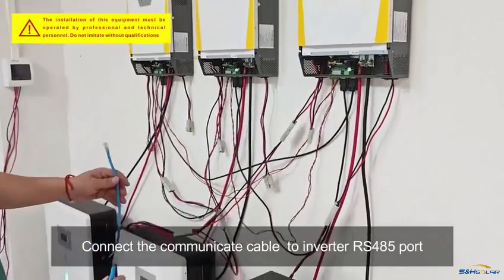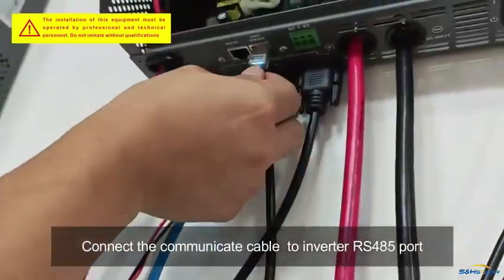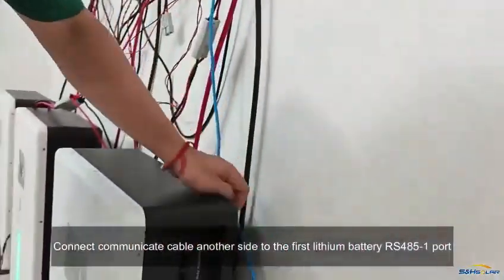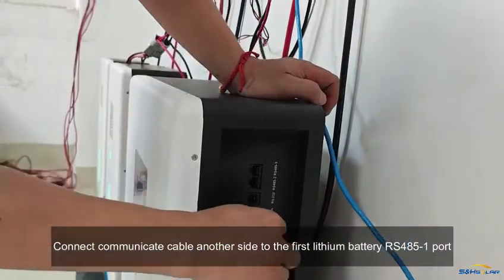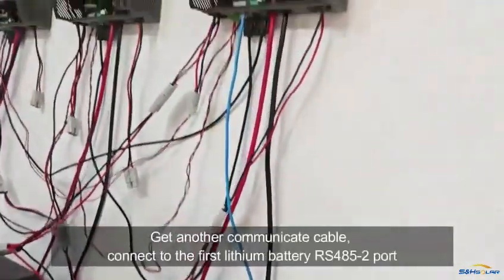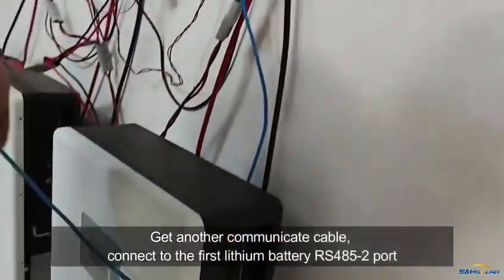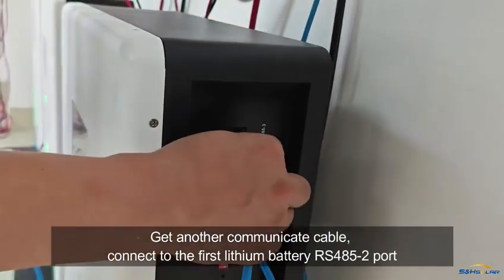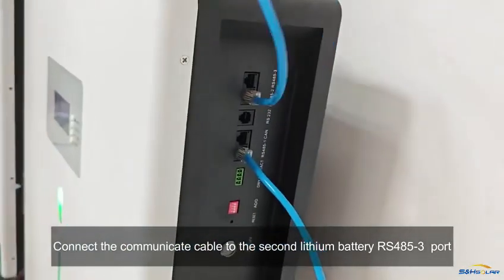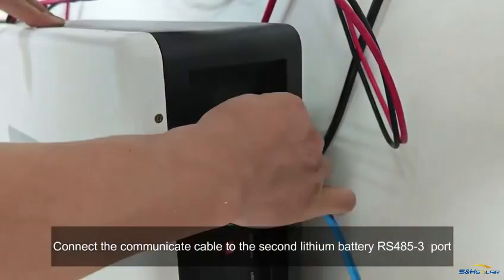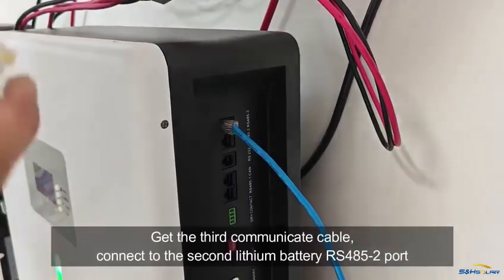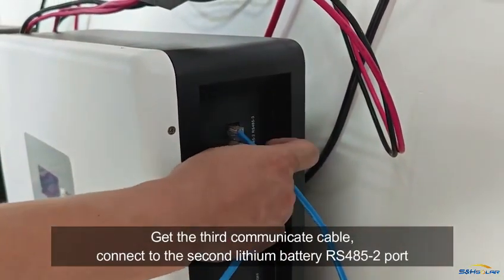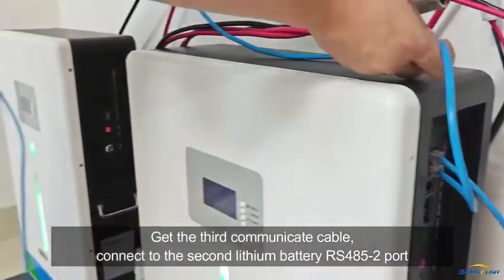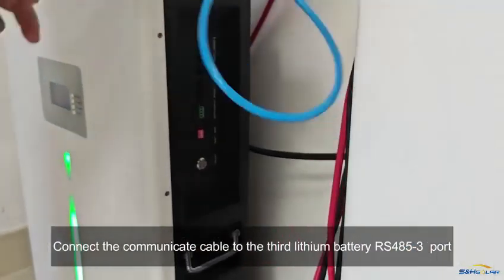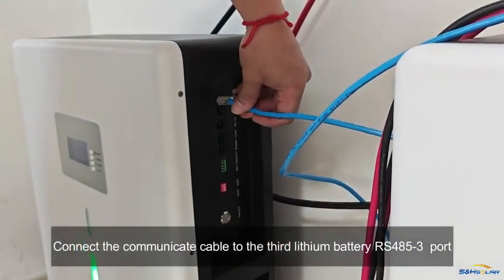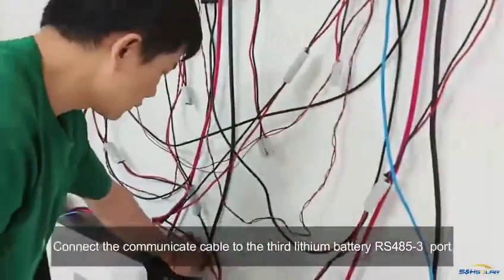Connect the communicate cable to inverter RS485 port. Connect communicate cable another side to the first lithium battery RS485-1 port. Get another communicate cable. Connect to the first lithium battery RS485-2 port. Connect the communicate cable to the second lithium battery RS485-3 port. Get the third communicate cable. Connect to the second lithium battery RS485-2 port. Connect the communicate cable to the third lithium battery RS485-3 port.